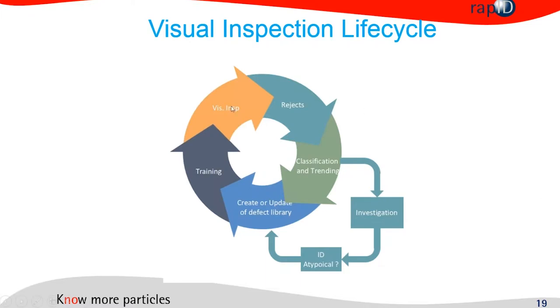In another view, we have visual inspection, the rejects, and after classification and trending — the level one check of particulate matter — you can trigger investigations and create and update a defect library. The defect library is really a starting point you need when implementing the 1790 life cycle, because it's used to train your inspectors and is the basis for classification and trending.